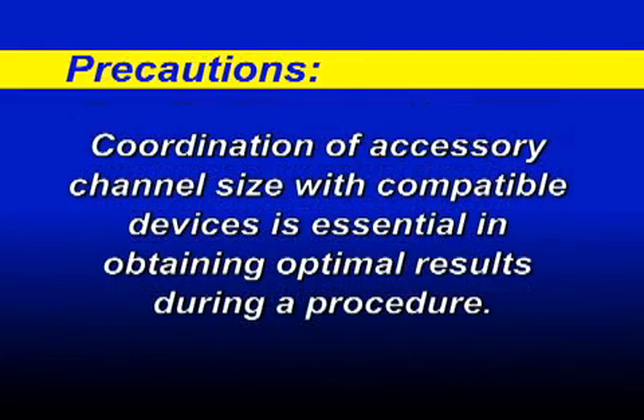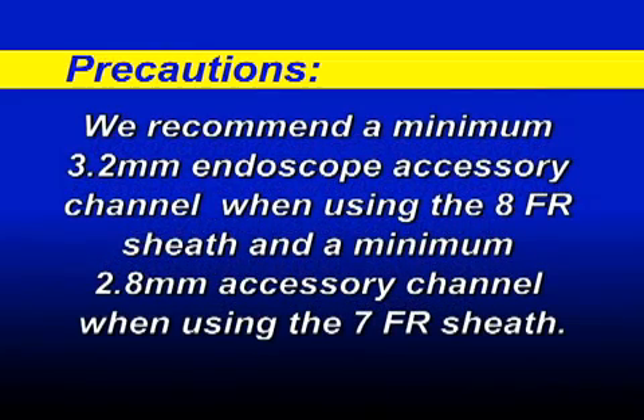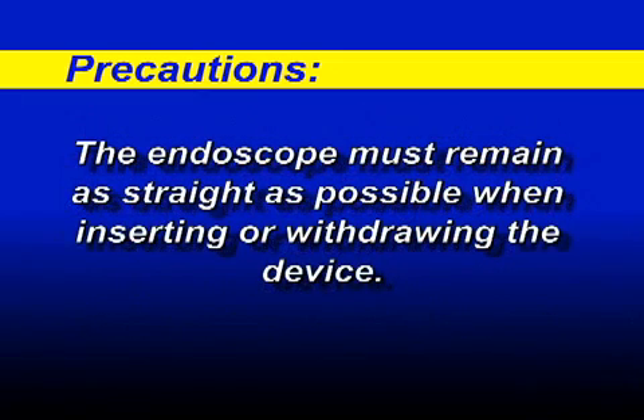The coordination of the accessory channel size with compatible devices is essential in obtaining optimal results during a procedure. We recommend a minimum 3.2 mm endoscope accessory channel when using the 8 French sheath, and a minimum 2.8 mm accessory channel when using the 7 French sheath. Refer to the product package label for the minimum channel size required for this device. The endoscope must remain as straight as possible when inserting or withdrawing the device.